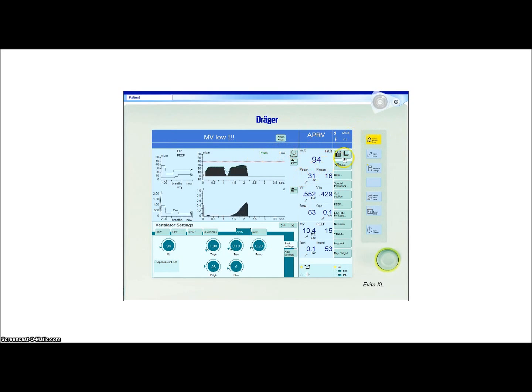Now the mean airway pressure, that can be increased to improve oxygenation. So this PMEAN, P-mean, that's the mean airway pressure. That's the mean pressure, not the inspiratory pressure. It's not the peak airway pressure, the peak inspiratory pressure. It's the mean pressure. If I want to increase that mean, I would come up here and increase the inspiratory pressure.